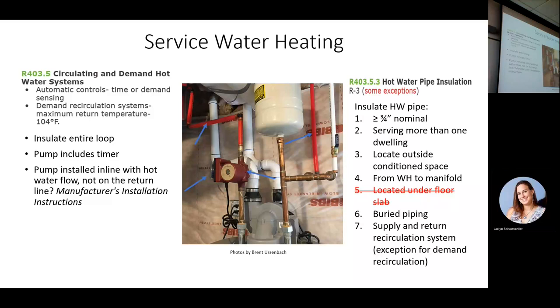So that's one of the places that hot water pipes need to be insulated. And what I'm talking about here is water heating for our potable water. This is the list that's in the code. By state amendment, they've said that you don't have to insulate the hot water pipes under the slab, which I disagree with, but that's what the legislature did because some plumbers complained that it was expensive to do it.